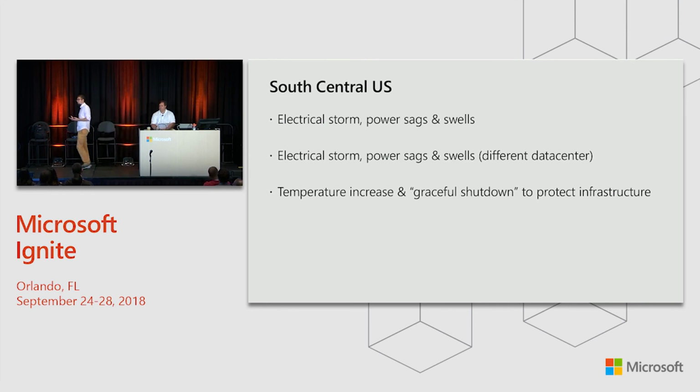It got so warm that the air handlers shut down because the data center thought there was a fire. So what does it think when there's a fire? Starve the room of any oxygen. So there's outside air coming in. Let's shut that down. Let's starve the fire of any oxygen. Let's call the emergency services as well, and all these automated things happen.